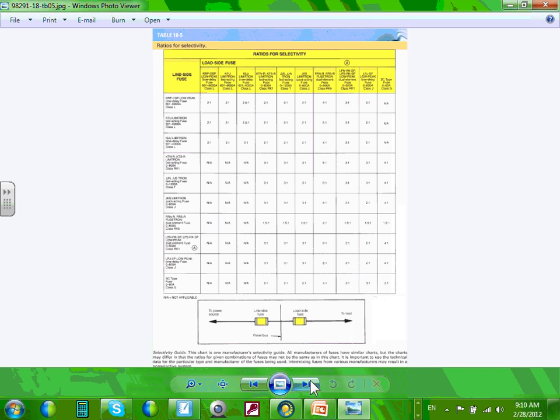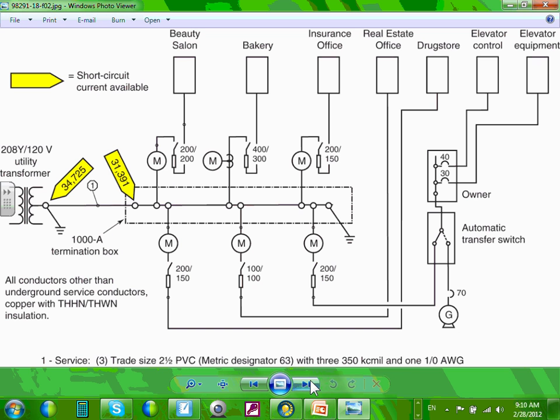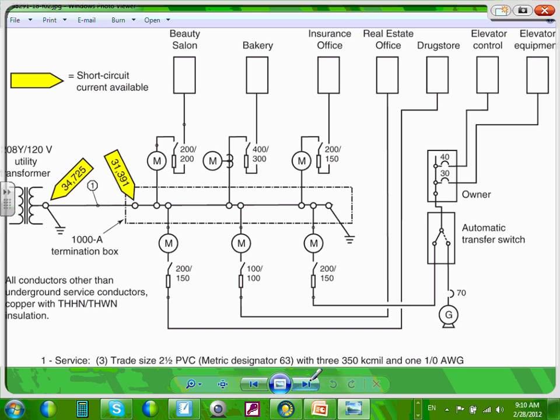All right, so let's go here. This is the riser, guys, for the system that we have in our building. Can you guys see it? Look at this. Right at the terminal of the transformer, I have almost 35 kiloamps. If I go downstream, it knocks it down to almost 31 kiloamps just by the impedance of the conductor.